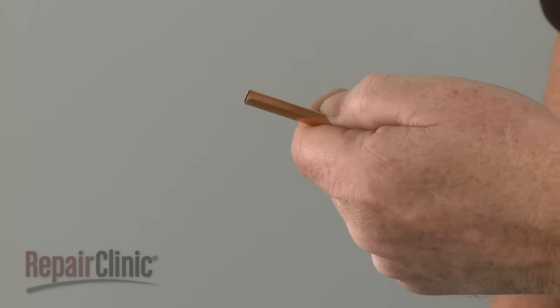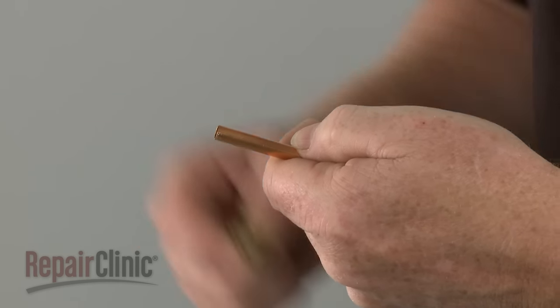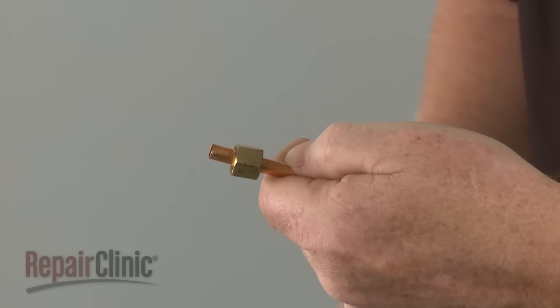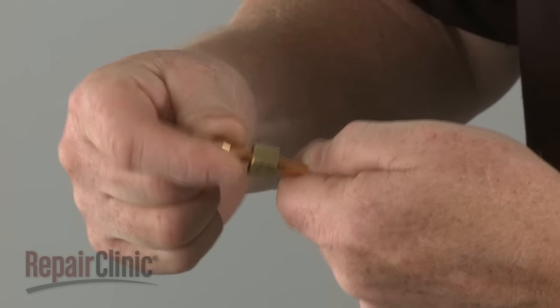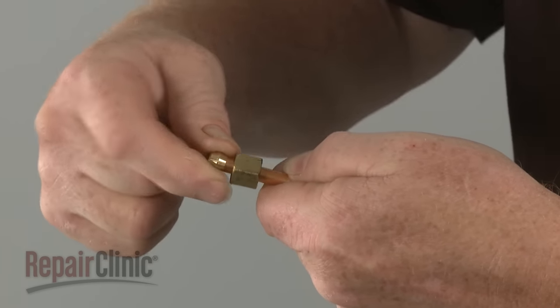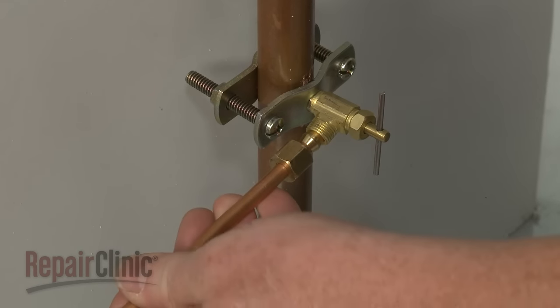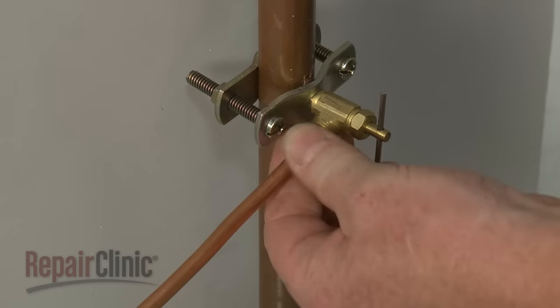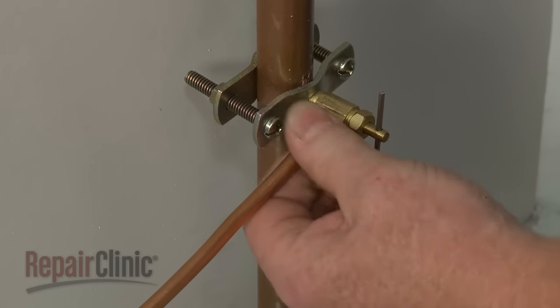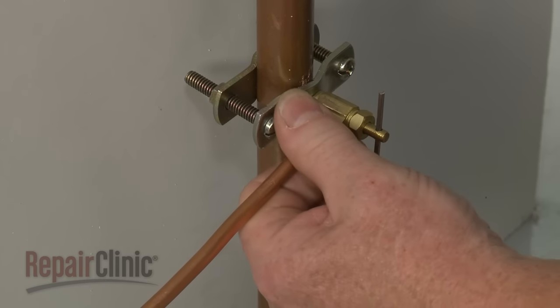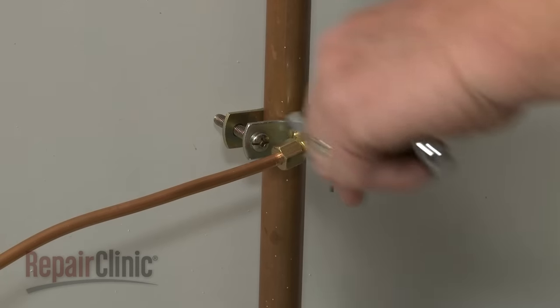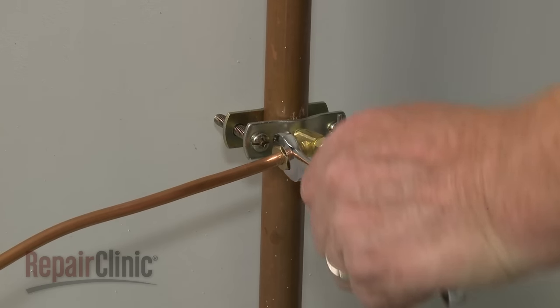After ensuring the end of the copper tubing is cut evenly and cleanly, slide on a compression nut and a compression sleeve. Now fully insert the tubing into the outlet connector on the shut-off valve. Thread and hand-tighten the compression nut. Use a wrench to tighten the nut one additional turn.